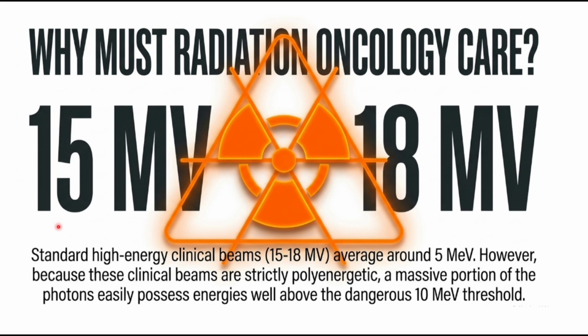Listen, when you set your linear accelerator to 15 megavolts, you are actually setting the maximum or peak energy of that beam as 15 megavolt. Because clinical X-ray beams are polyenergetic, they do not contain photons of just one single energy of 15 megavolt. Instead, they consist of a wide spectrum of different photon energies ranging from very low energies all the way up to that 15 MeV peak.